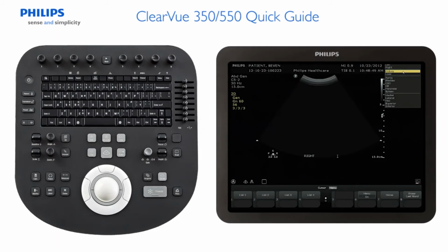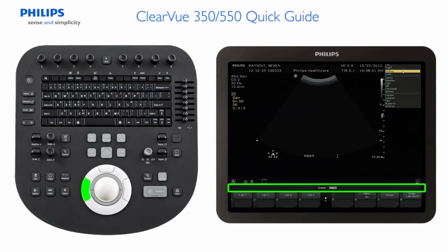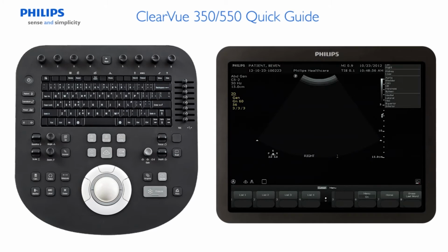To move a label to a different place on the screen, press the left trackball button to select Mode. Position the pointer over the label until it changes to a bold appearance. Press the middle trackball button to activate the word so that it changes to amber. Then use the trackball to move it to a new location. Once the label is in the desired location, press the middle trackball button to set the label on the image.